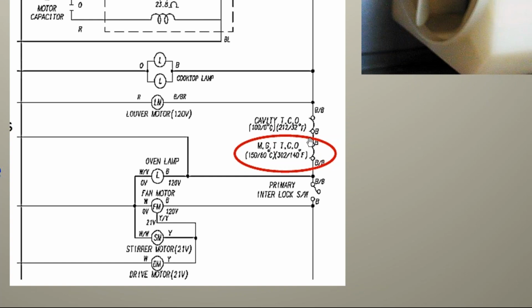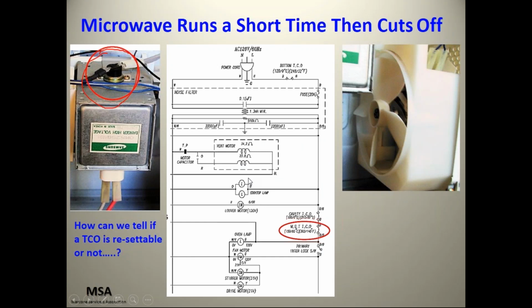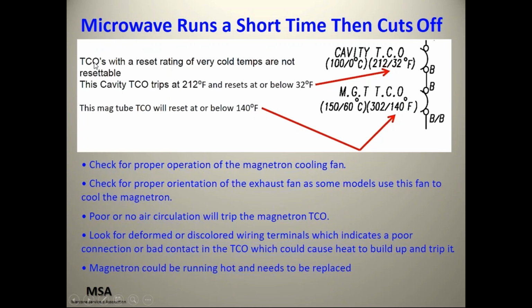The code that they use for TCOs as to whether they're resettable or not is, if it has a very low temperature for the reset temperature, it's normally not resettable. If it has a high temperature, it normally is. Okay, TCO, and they explain it probably better than I do. TCOs with a reset rating of very cold temperatures are not resettable. This cavity TCO trips at 212, resets at or below 32 degrees. The mag tube TCO will reset at or below 140 degrees.